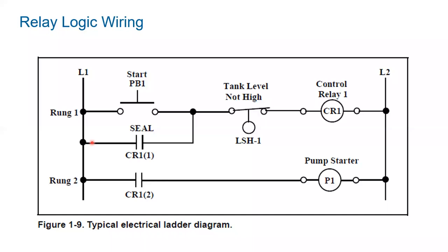So what we do is we create what's called a latch circuit. So we use this control relay right here, a contact off this control relay, and we actually put it in parallel to the push button. So now when I press the push button, I energize the relay, this contact closes, and now I have this parallel path and keeps its own self energized.